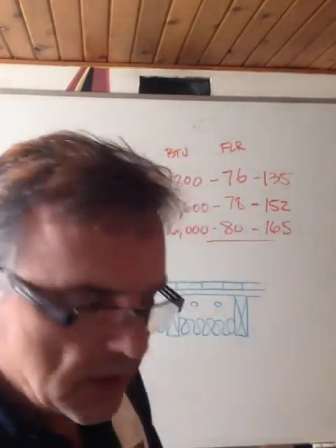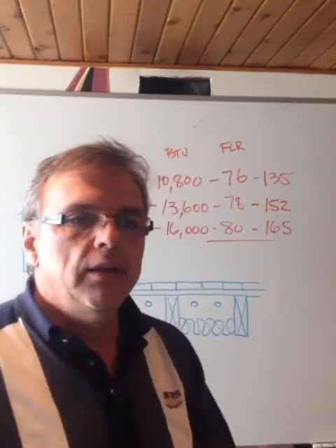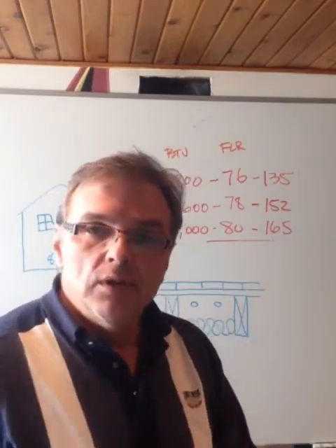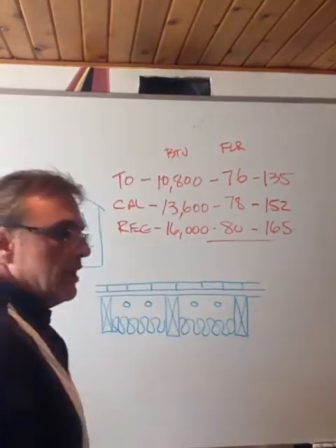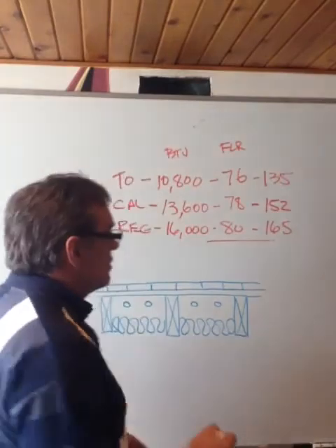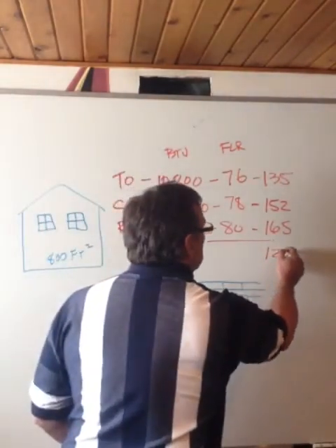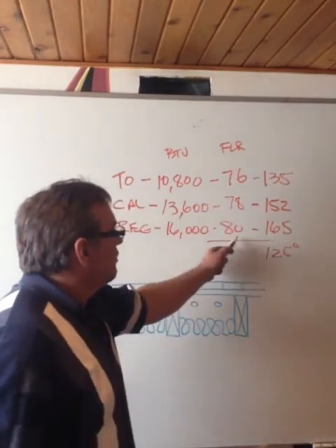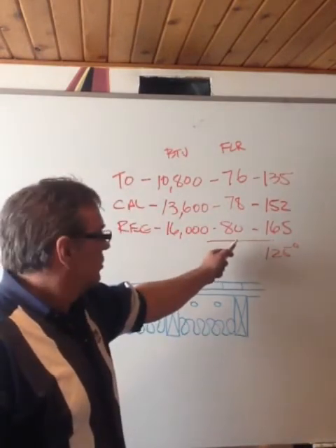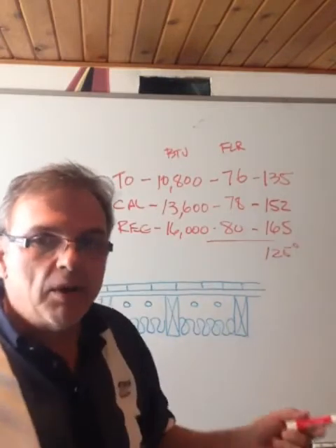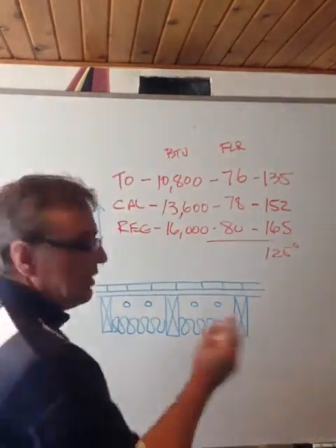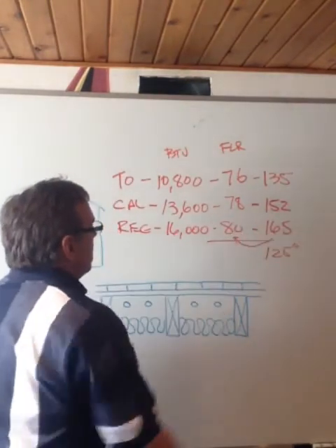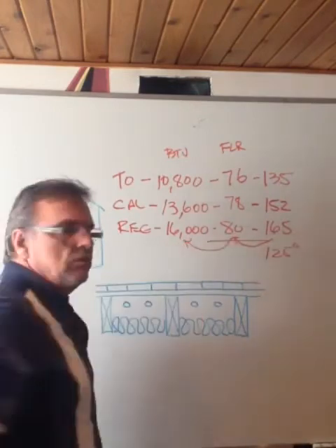The installer has been taught that radiant heat runs very efficiently and inexpensively at low temperature. So what does he do? He puts a tempering or a mixing valve of some sort on the system, and he tempers that water down to 125 degrees. Well, at 125 degrees you can never achieve the desired surface temperature of 80 degrees for the vast part of the winter. You need to have 165 to reach the surface temperature of 80 to meet the BTU load, correct?